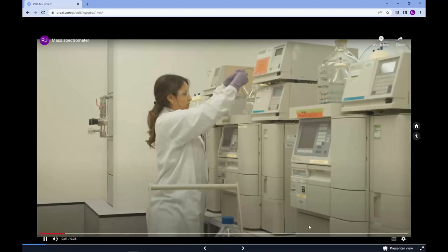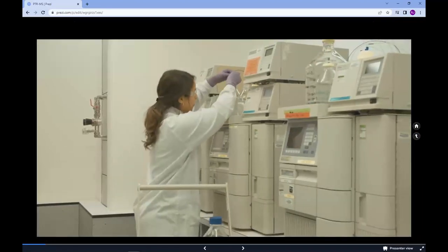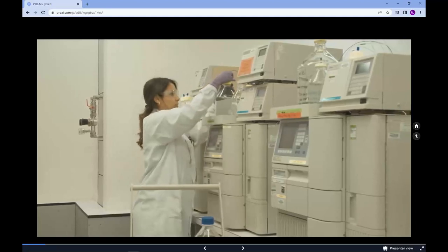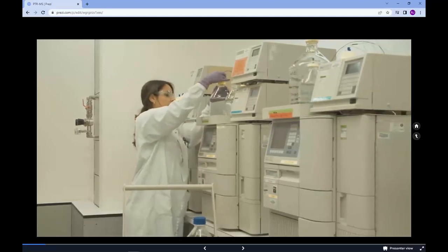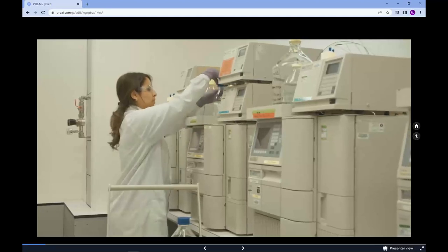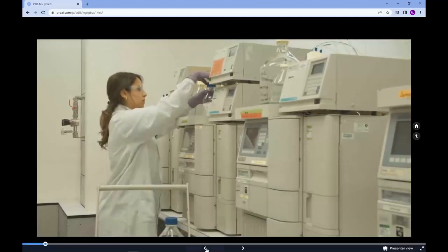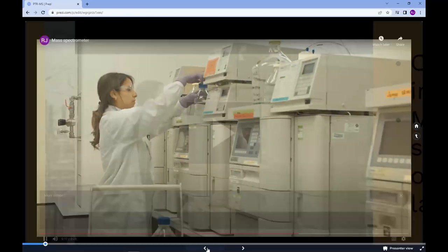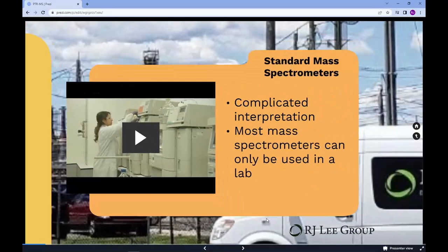Analysis using a mass spectrometer commonly results in fragmentation of larger molecules into smaller ones, complicating the interpretation, as the pattern of the fragmented masses needs to be identified and used towards the identification and quantification of the original larger molecules. The delicate nature of these analytical operations requires that most mass spectrometers can only operate within the confines of a laboratory, analyzing discrete samples introduced into these instruments.